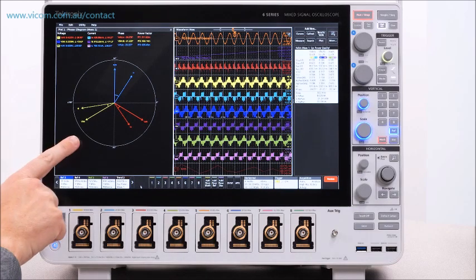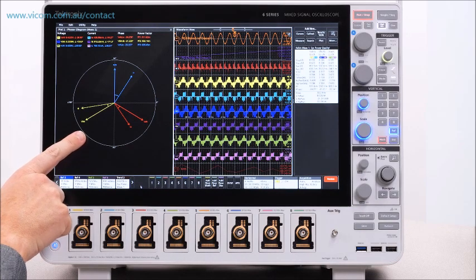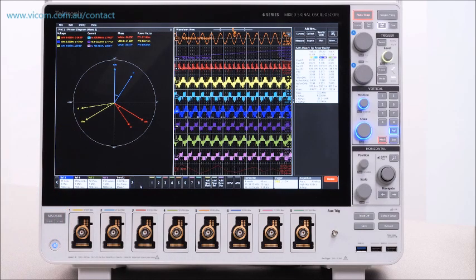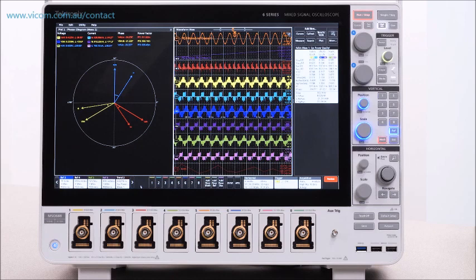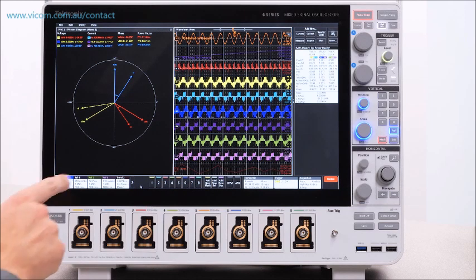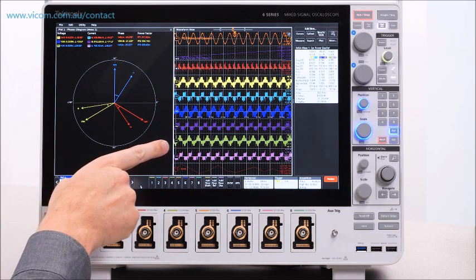Phasor diagrams show currents and voltages at a glance to help verify your connections or quickly spot imbalances. And most importantly, the package lets you make stable power measurements on tricky 3-phase PWM waveforms.